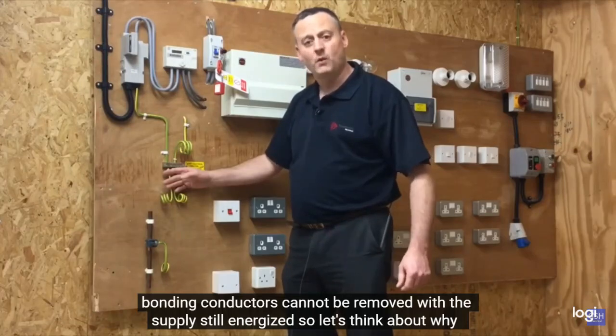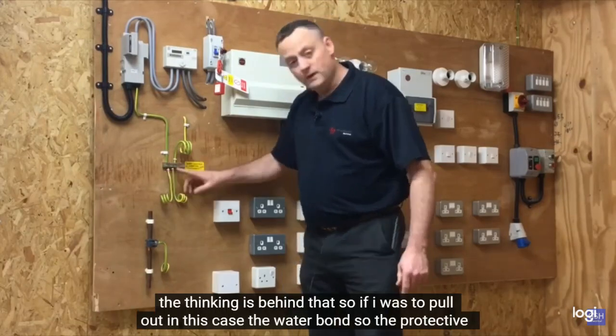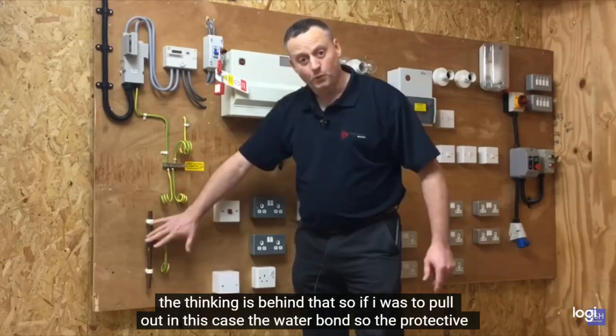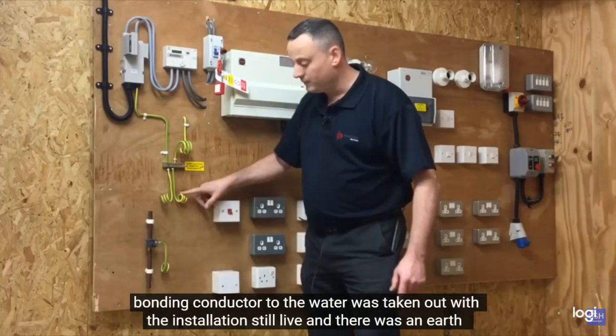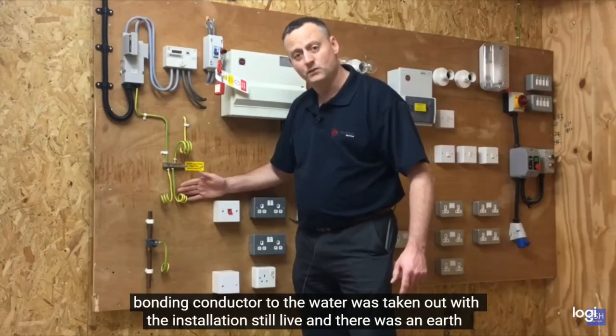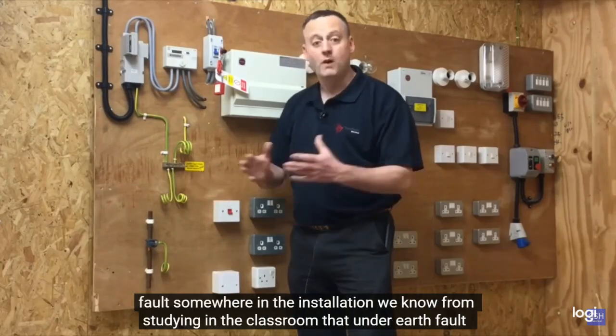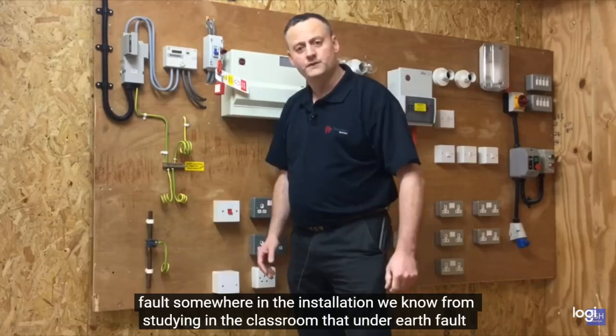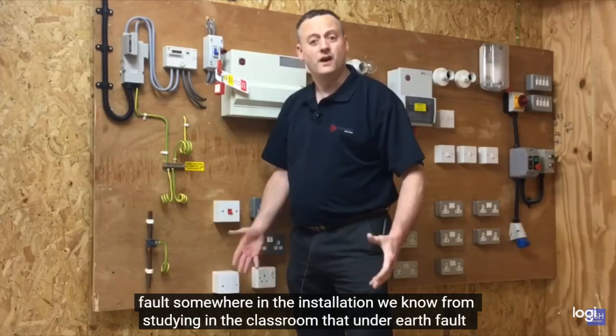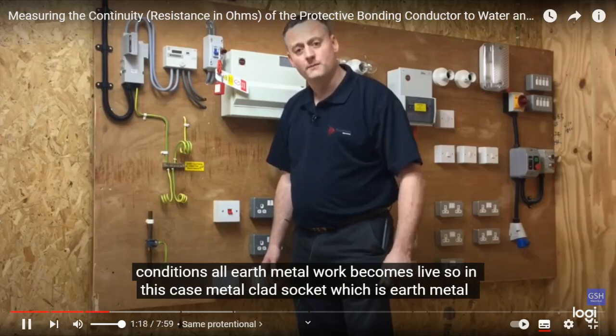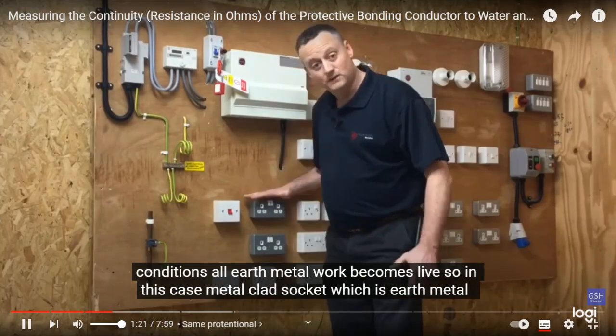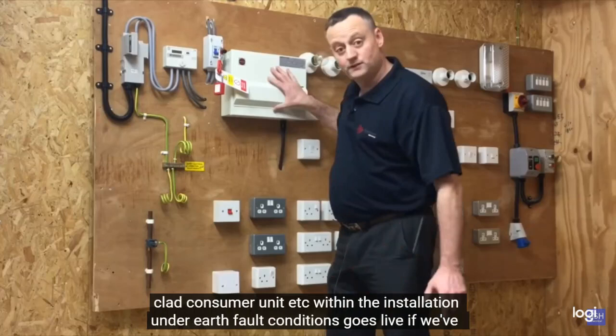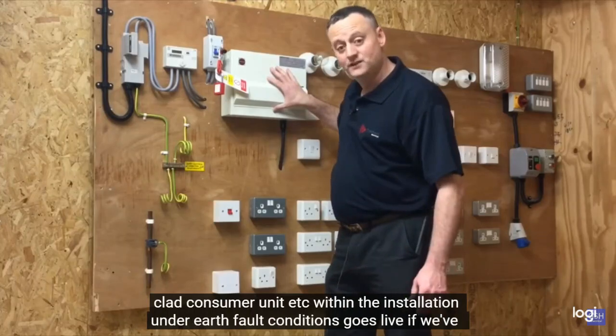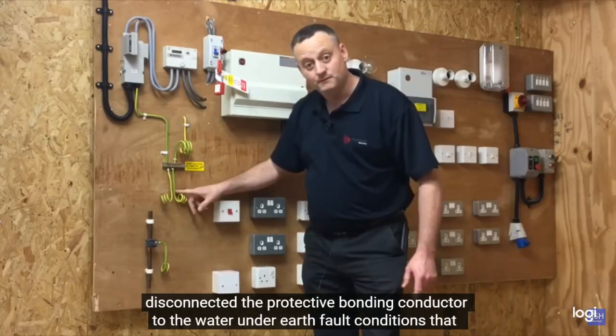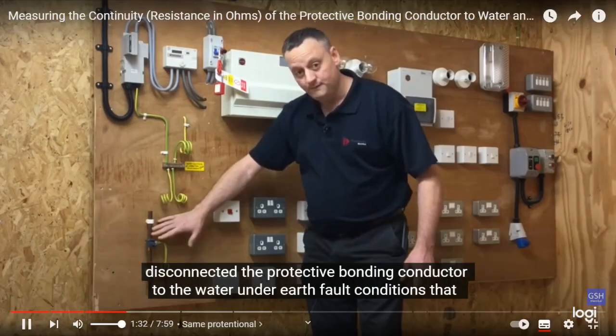So let's think about the thinking behind that. If I was to pull out the protective bonding conductor to the water while the installation was still live, and there was an earth fault somewhere in the installation, we know from studying in the classroom that under earth fault conditions, all earthed metalwork becomes live. So in this case, the metal clad socket, which is earthed, the metal clad consumer unit, etc., within the installation goes live under earth fault conditions.